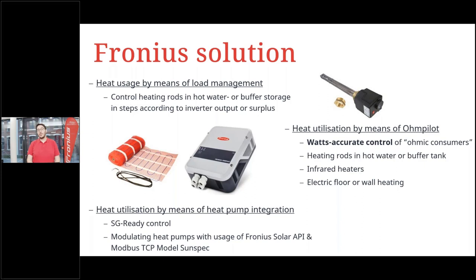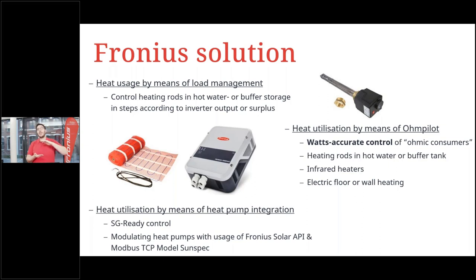For connecting a heat pump to the PV system, Fronius offers several solutions. There are two possibilities: one is Smart Grid Ready (SG Ready), an input on the heat pump that lets you give a control signal — switch on now or increase the target temperature for two hours. There are also some heat pumps that receive surplus information via the Fronius PV system and can modulate their power to the level of the surplus. This is similar in concept to the Ohm Pilot but controlling a heat pump instead.